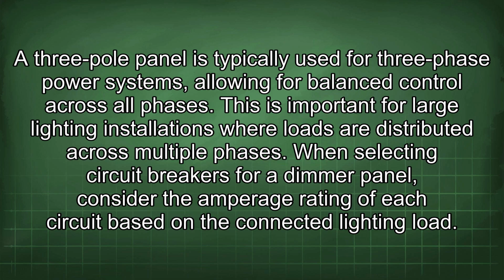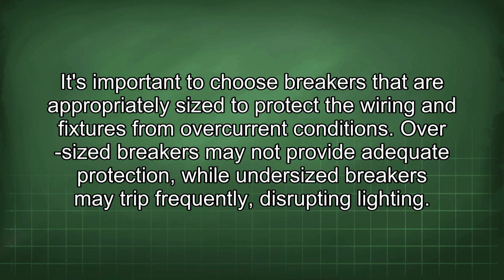When selecting circuit breakers for a dimmer panel, consider the amperage rating of each circuit based on the connected lighting load. It's important to choose breakers that are appropriately sized to protect the wiring and fixtures from overcurrent conditions. Oversized breakers may not provide adequate protection, while undersized breakers may trip, frequently disrupting lighting.